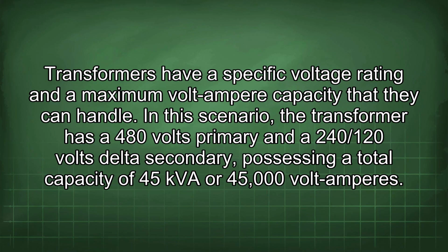Transformers have a specific voltage rating and a maximum volt-ampere capacity that they can handle. In this scenario, the transformer has a 480 volts primary and a 240/120 volts delta secondary, possessing a total capacity of 45 kVA or 45,000 volt-amperes.